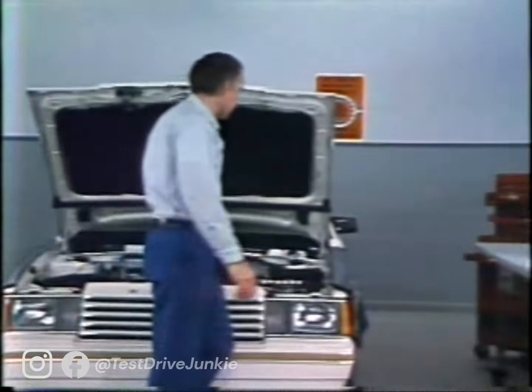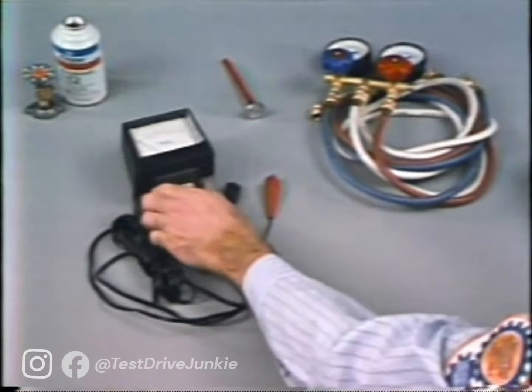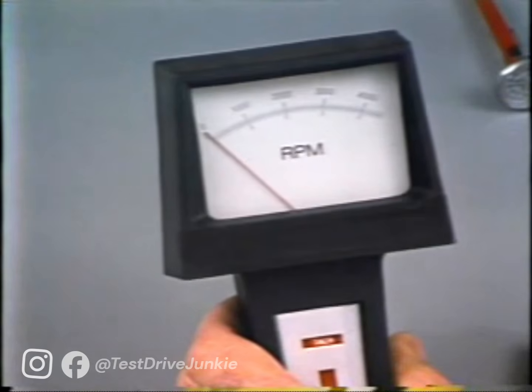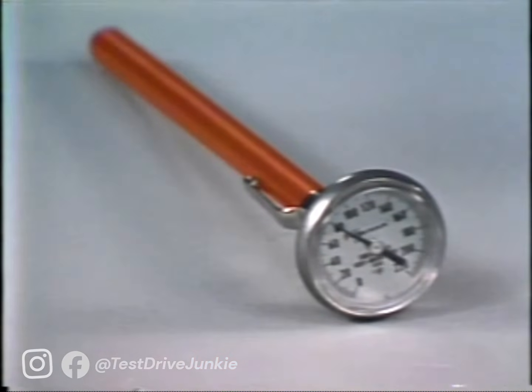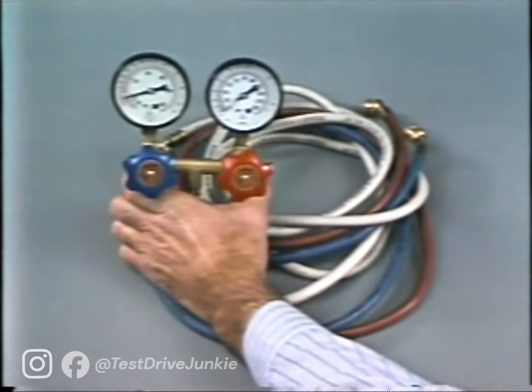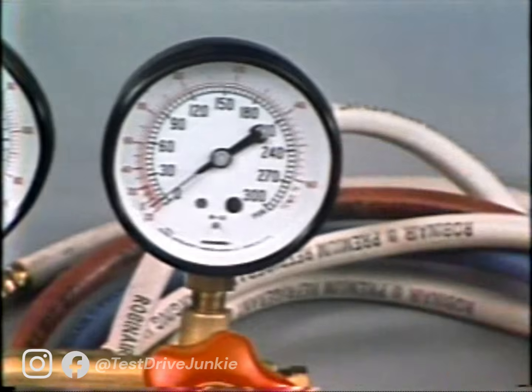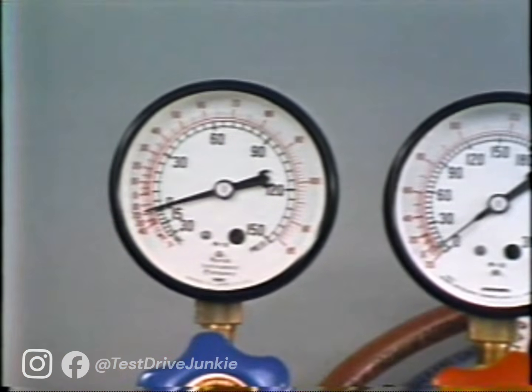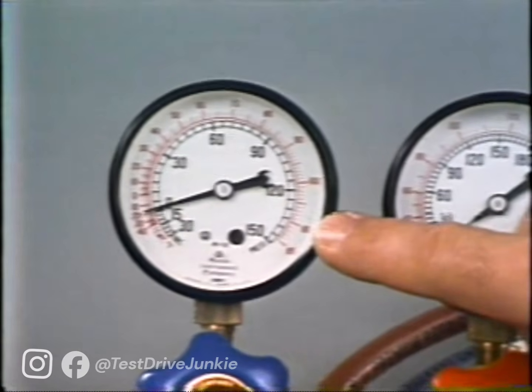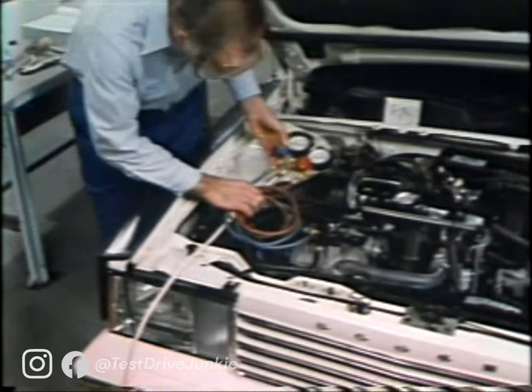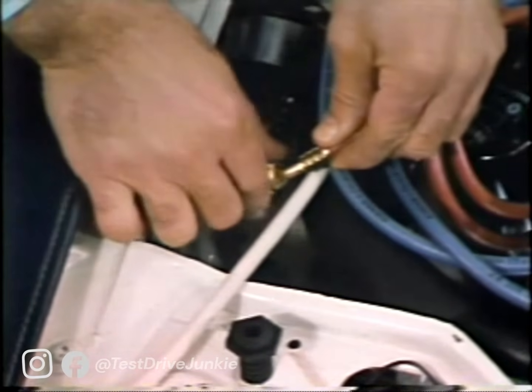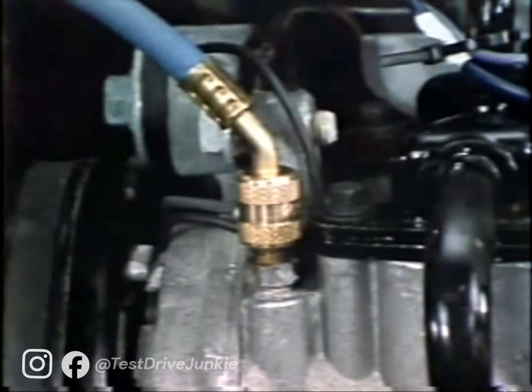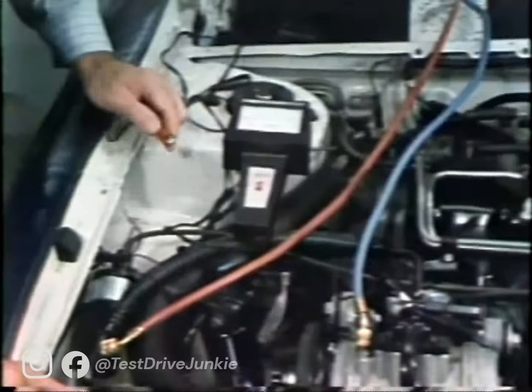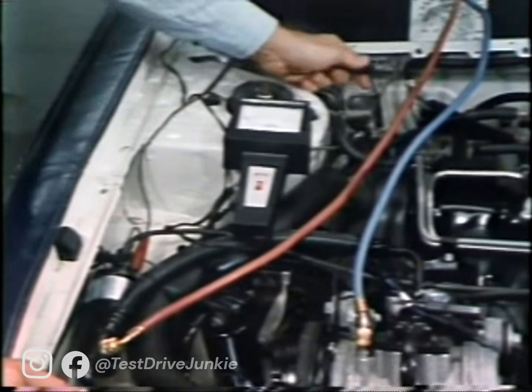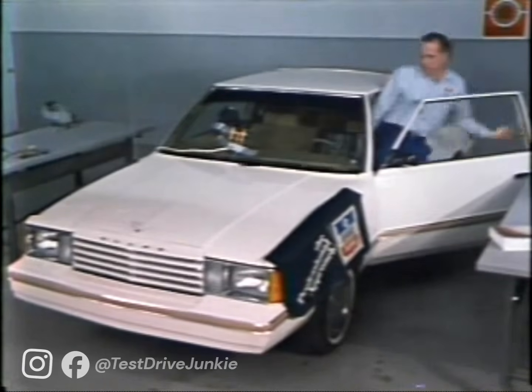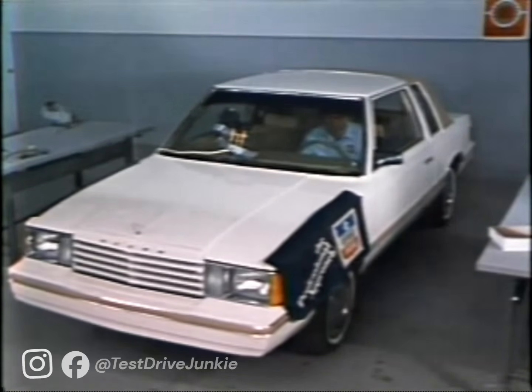The operation checks haven't revealed the source of the problem, so we'll have to conduct a performance test. To perform the test, you'll need a tachometer, an accurate thermometer, and an AC manifold gauge set. Note that only two gauges, a discharge pressure gauge and a suction pressure gauge, are used instead of the 3 gauges used previously. Connect the discharge pressure gauge to the discharge service port on the muffler, and connect the evaporator suction gauge to the suction port of the compressor. Then, connect the tachometer and close the hood, doors, and windows.